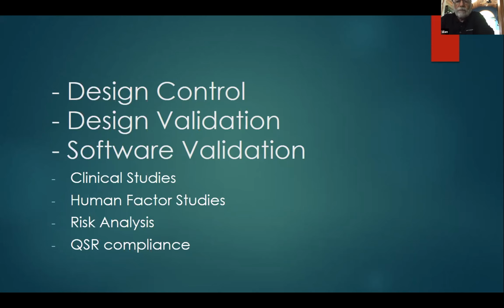So you're going to have your clinical trials as part of the software validation. You're going to have your human factor studies. You have to do a risk analysis. And as part of any new medical device company, you have to be QSR, quality system regulation, compliant. That's 21 CFR 820. 21 CFR 820 is the FDA regulations, the quality system regulations, for the manufacturing and design of medical devices. Excuse me.